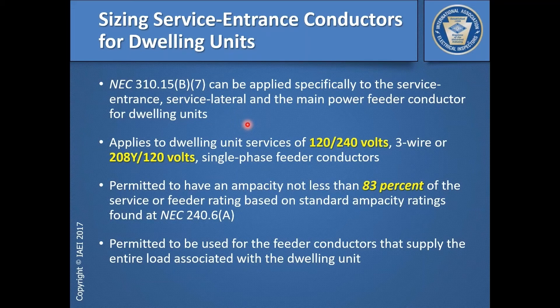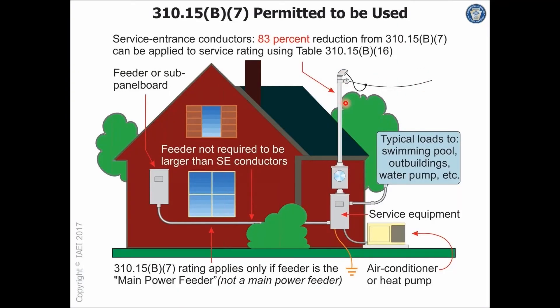You can also apply that 83% load calculation to a feeder if that feeder provides power to the entire dwelling unit. So how could you have more than one feeder where it still provides power to the entire dwelling unit before you could use the derating factors of 310.15(B)(7)? You'd be able to size the service entrance conductors using 310.15(B)(7) and its 83% load calculation.